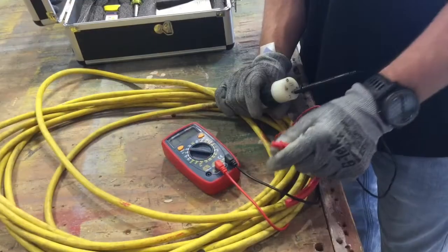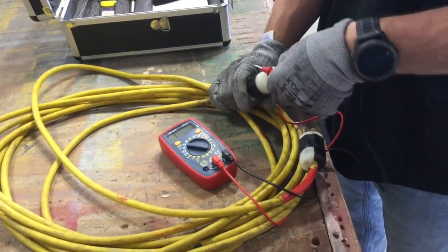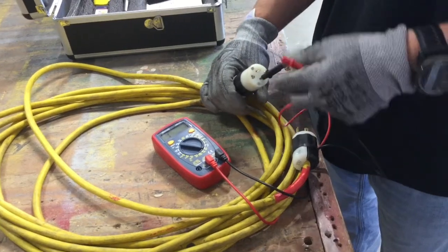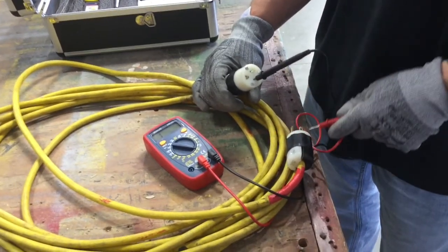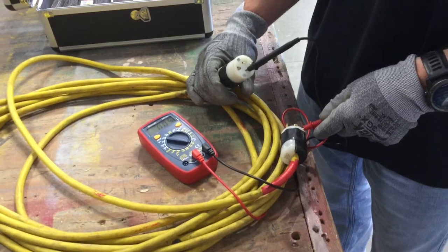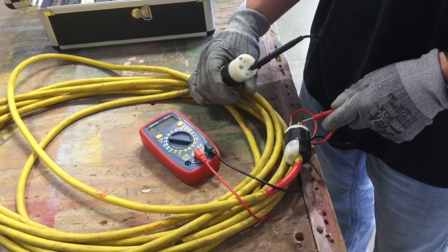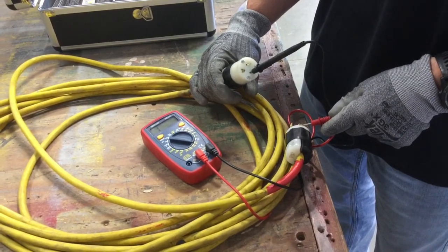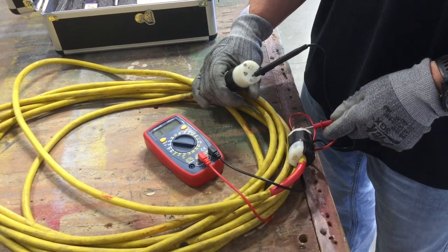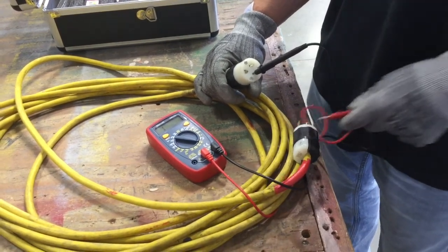Test hot conductor for continuity with neutral conductor. There should be no continuity. Test hot conductor on male side of cord for continuity with hot conductor on female side of cord. There should be continuity. If there is no continuity, the hot and neutral conductors on one side of the cord are reversed and need to be fixed.